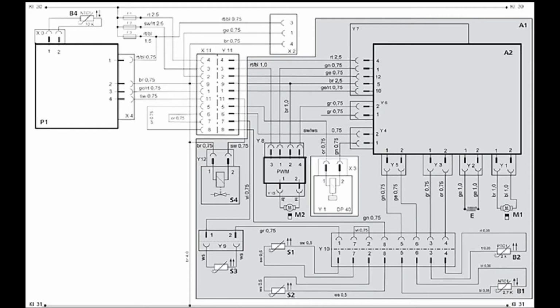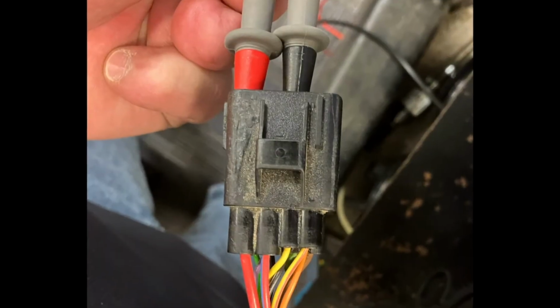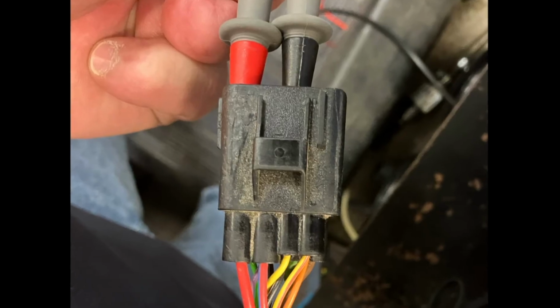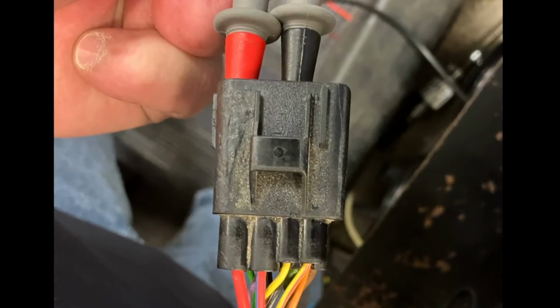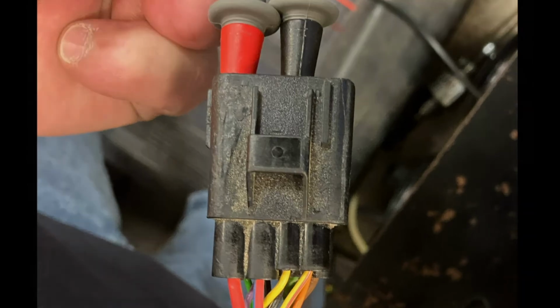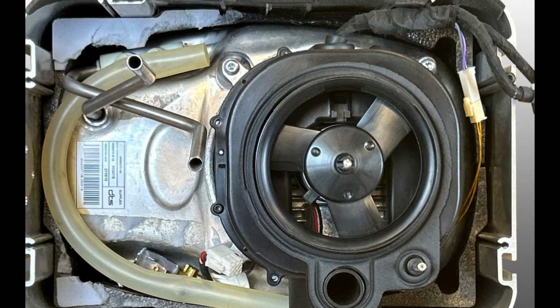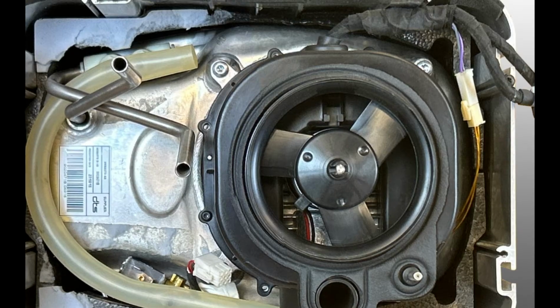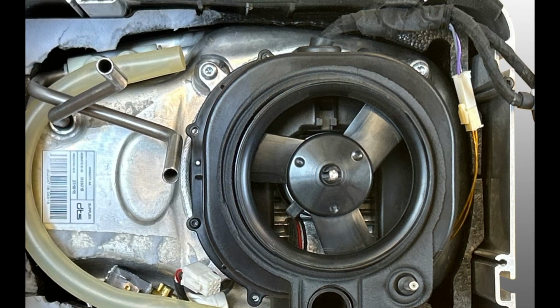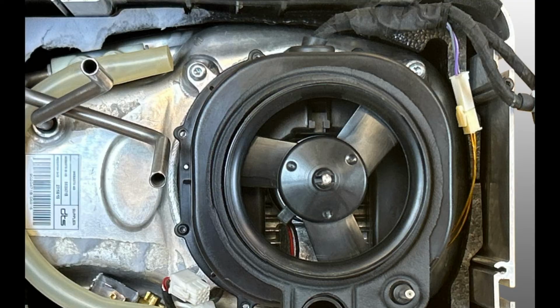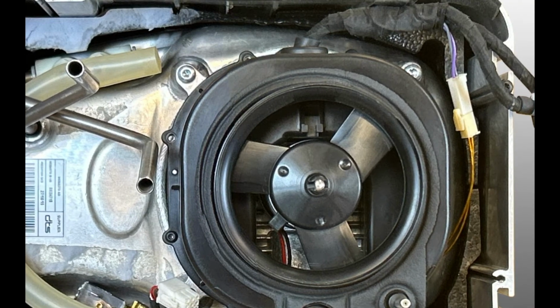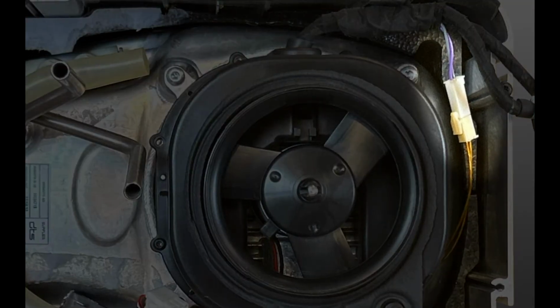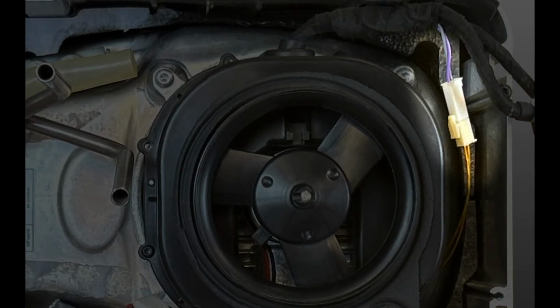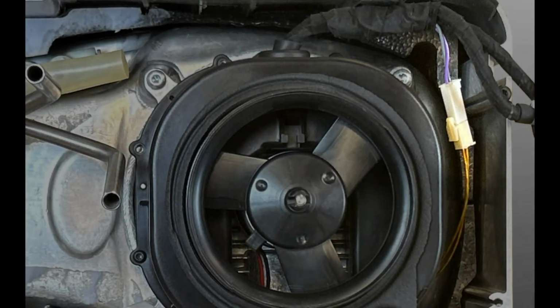You can easily check the continuity of all 3 of these switches at the Y11 connector right at the heater itself using your digital volt ohm meter or DVOM. These are switches we're dealing with, not sensors, so we're simply looking for continuity between pins 7 and 8. To check the switches individually, you'll need to take the front cover off the heater. To check the combustion overheat switch, you can use a DVOM to check for continuity at the Y9 connector. This is the white 2-pin connector that has 2 gold braided wires on one side of the connector.